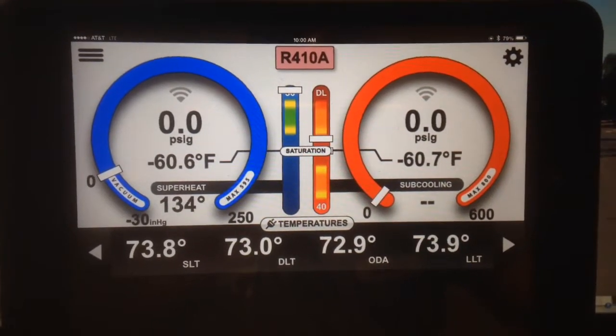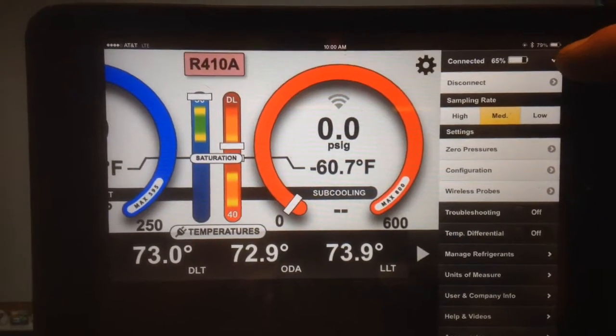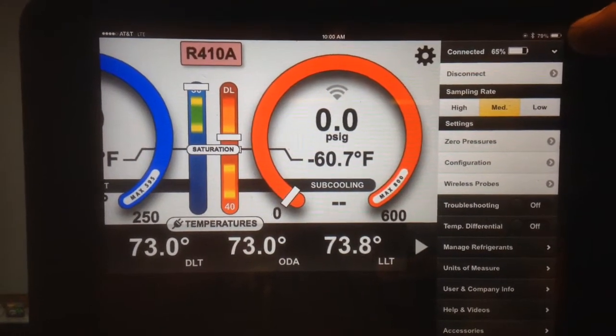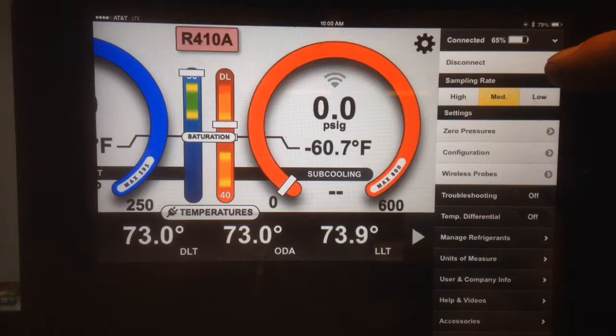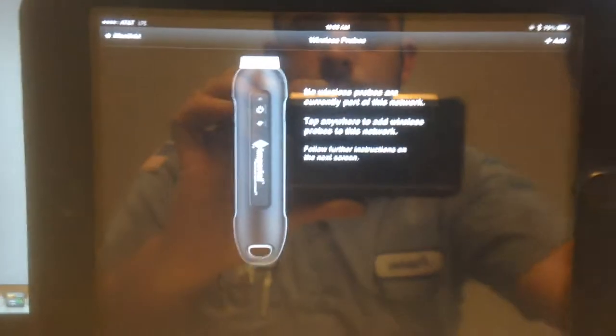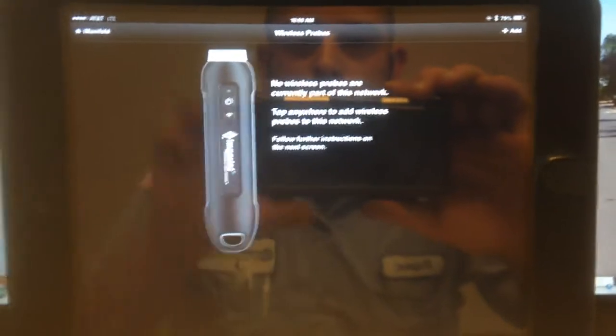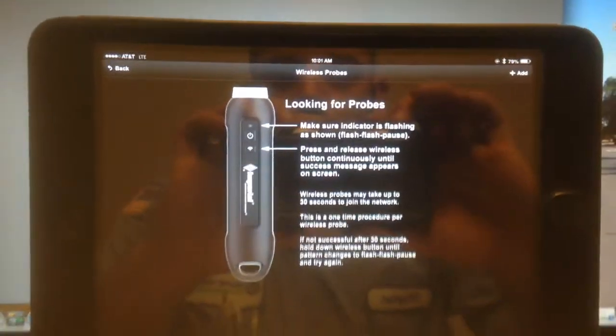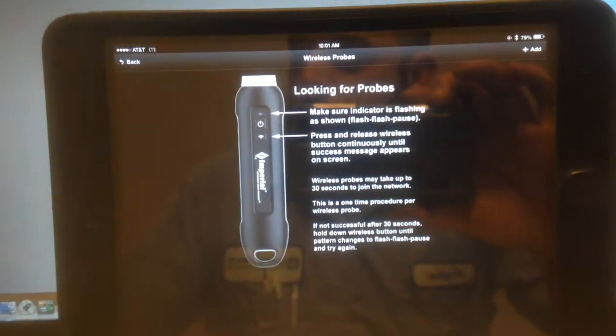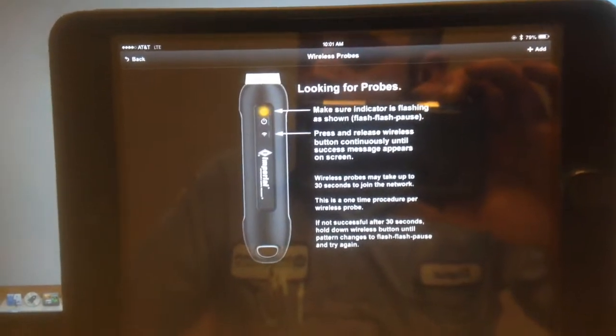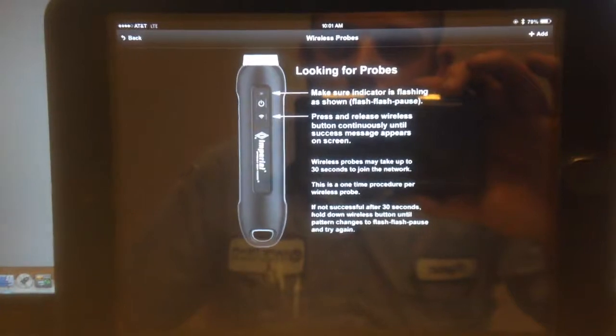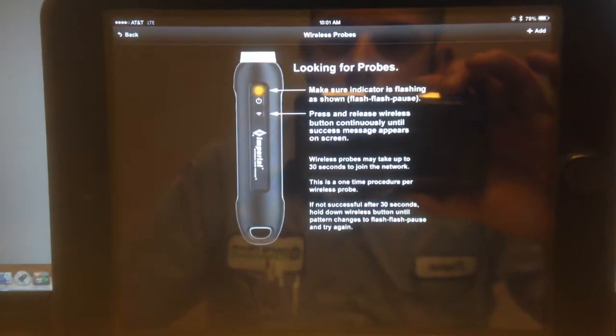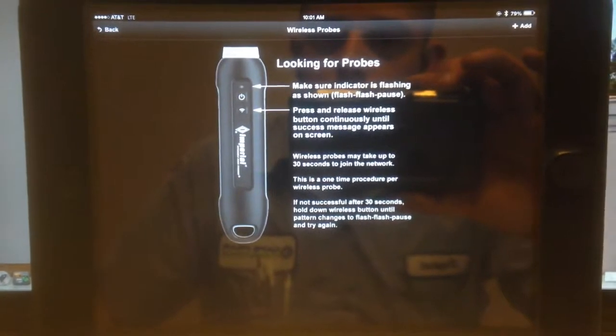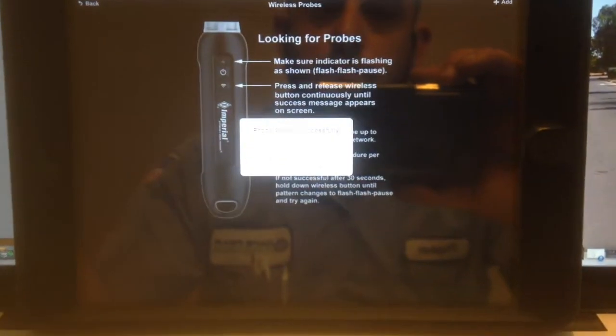Alright, so we are in the iManifold app. We are already connected. As you can see, we've got liquid line, outdoor, and delta or discharge. Going to go into wireless probes. You can see me in the camera there. We are going to add, and we're going to start with the temperature probe that we want to use for supply. We are looking for probes. We're going to press and release the wireless button until we get a notification telling us that we are connected. We have success.